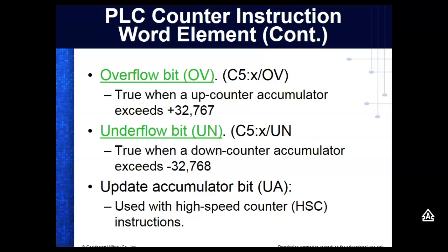These are hard. What they found out is that these counters are programmed. So we come over here and we put a counter. But over here, this is going to be a machine code program, and it's going to be very, very long when this is downloaded into the PLC. So we tell it a counter, but the counter has to run a machine language program that could be very long. And what was happening is that when we were counting, we would miss counts. If we tried to count extremely fast, the program could not keep up with what we were trying to count.